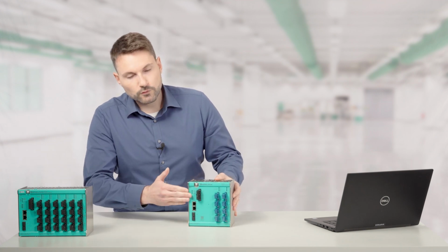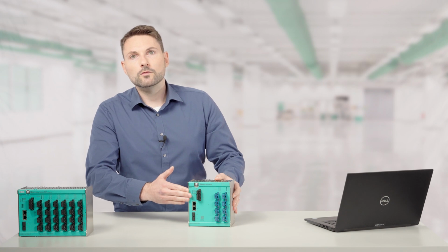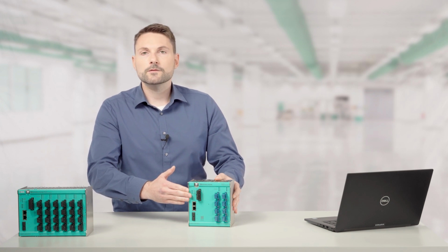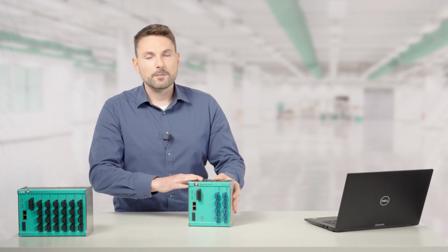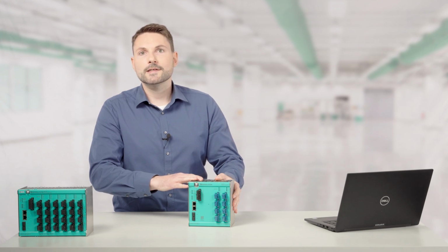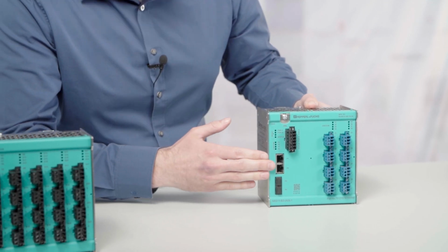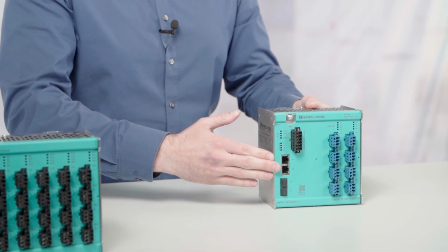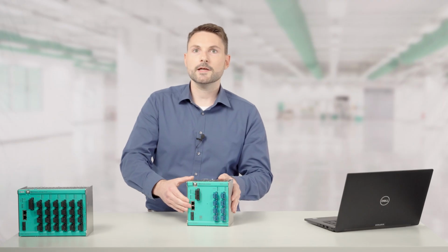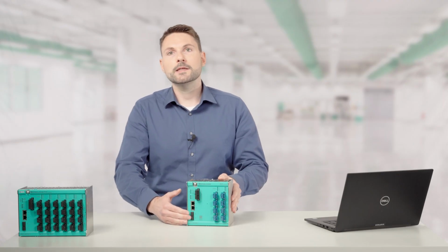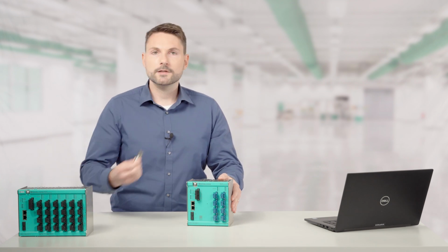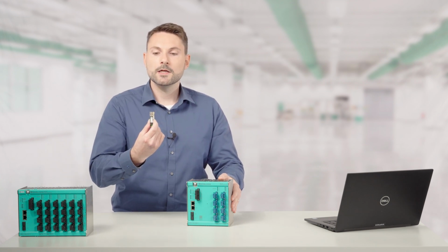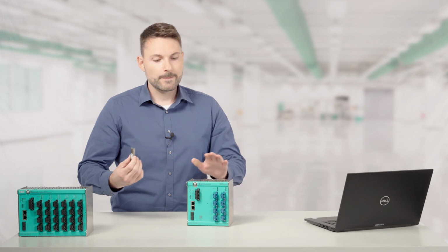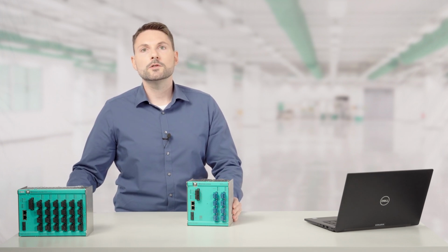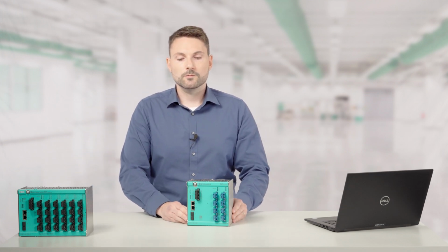Each switch can be supplied by either a single or redundant power supply. The switches expect a power supply of between 20 and 60 volts DC. We also have two RJ45 network connection ports for connecting the local area network and two SFP module slots. Here, SFP modules can be plugged in to connect fiber optic cables. The devices support both multi-mode and single-mode modules.